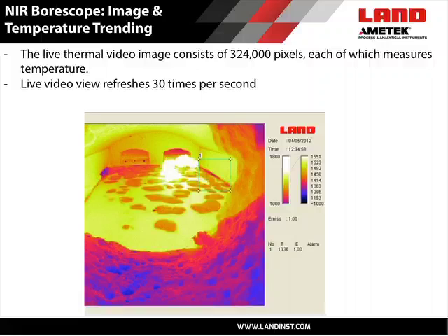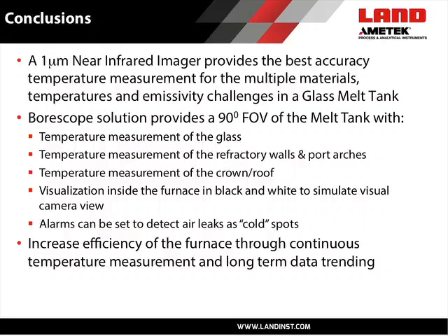Here's a Land NIR-B imager looking into an end-fired glass tank. You can see here that right now the tank is being fired from the right-hand port. The video image is a live image, refreshing 30 times a second, just like a video camera, but also giving you full temperature measurements anywhere within the scene. A DVR function within the software can save time-lapse videos, which make it very easy to detect and spot developing trends. So let's summarize what we've seen.